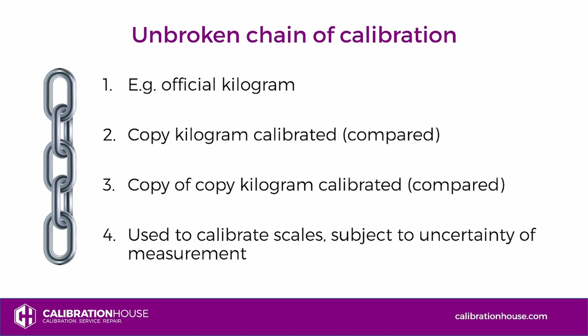Now, are you uncertain about uncertainties of measurement? This is defined as the doubt that exists about any given measurement. It is statistically derived, taking into account all factors that could affect the calibration process. These are normally environmental, so it can be temperature, it can be humidity. So for the 3 different kilograms that we just discussed, you might have an uncertainty of measurement for your final kilogram of 0.2 milligrams plus or minus, which you can then take into account when looking at your readings.